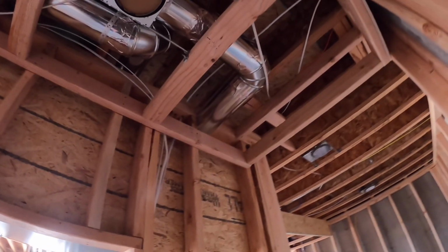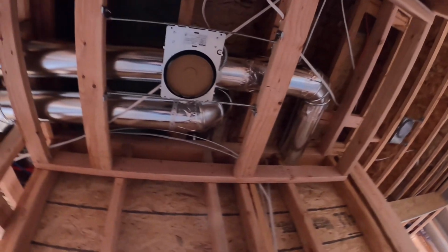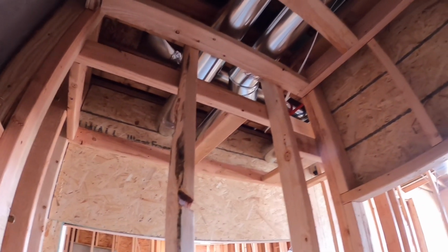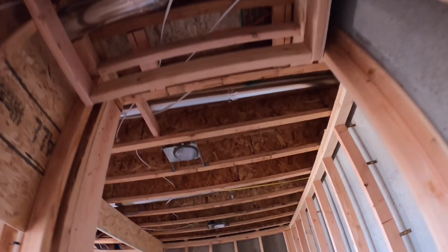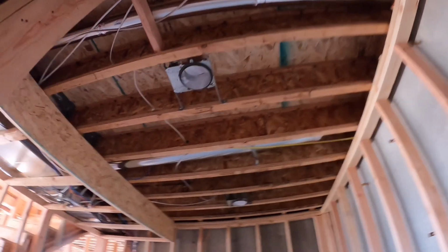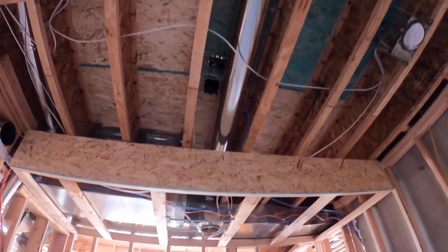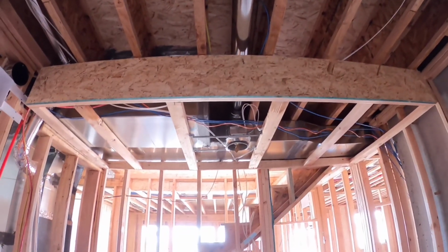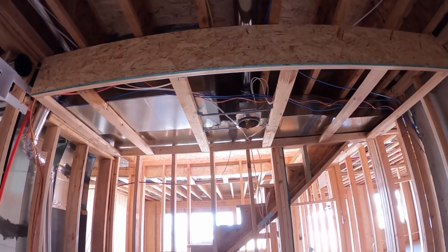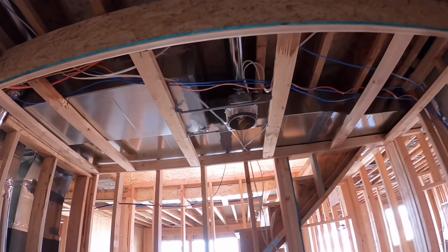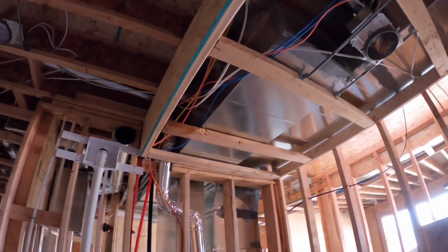So kind of the cutoff we have for one furnace to two furnaces is typically around 3,500 square feet. Bigger than that, you probably ought to go with two furnaces. Smaller than that, you can get away with one. There's definitely a balance between a one furnace home in, let's say, a basement and a single level home because it's hard to balance those two. Typically, they say it's about an 8-degree difference per level of a home just because you're higher and the hot air rises and more solar thermal input and so forth. So you got to take that in perspective as well.